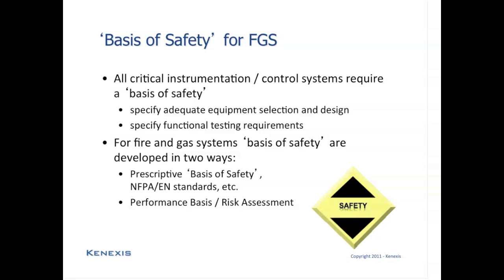Okay, all safety instrumentation needs a basis of safety, including fire and gas systems, FGS, fire and gas detection and suppression systems. And what we mean by a basis of safety is that some sort of standard or some sort of procedure, some sort of process needs to be available to ensure that the adequate equipment is selected and designed for the process that is under control, that is under study. So some sort of process needs to be available to make sure that if a fire and gas detection and suppression system is required, it will be implemented. The design will provide the appropriate amount of detectors, that those detectors will be in the correct location, and that the proper technology will be selected.